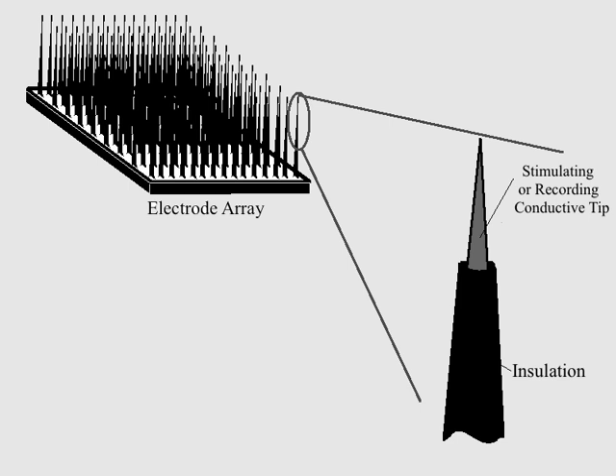Electrode fouling is a major hindrance on the performance of electrodes. Few materials are completely bioinert, as in they trigger no bodily reaction. Some materials that may be bioinert in theory fail to be ideal in practice because of defects in their formation, processing, manufacturing, or sterilization. Fouling can be caused by adsorption of proteins, fibrous tissue, trapped cells or dead cell fragments, bacteria, or any other reactive particle. Protein adsorption is influenced by the nature and geometry of domains including hydrophobicity, polar and ionic interactions of the material and surrounding particles, charge distribution, kinetic movement, and pH.